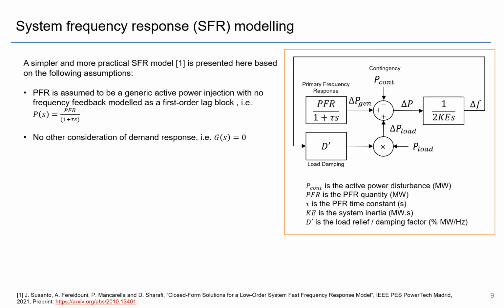Everything's firstly in natural quantities, so megawatts and hertz, and there are some other attractive features to this model that make it a bit more useful from a practical standpoint, or at least just from doing simulations. So I'll walk you through the model. So first of all, this is just the inertia block, and damping is excluded or external to that inertia block. And it's just an input into the active power deviation. The other thing to note is that the primary frequency response has no feedback to frequency, so it's literally just a generic active power injection.